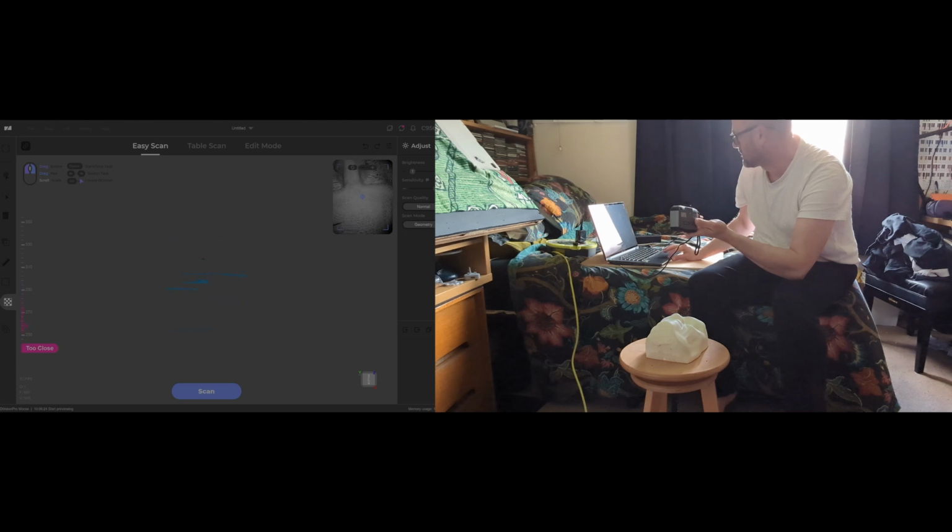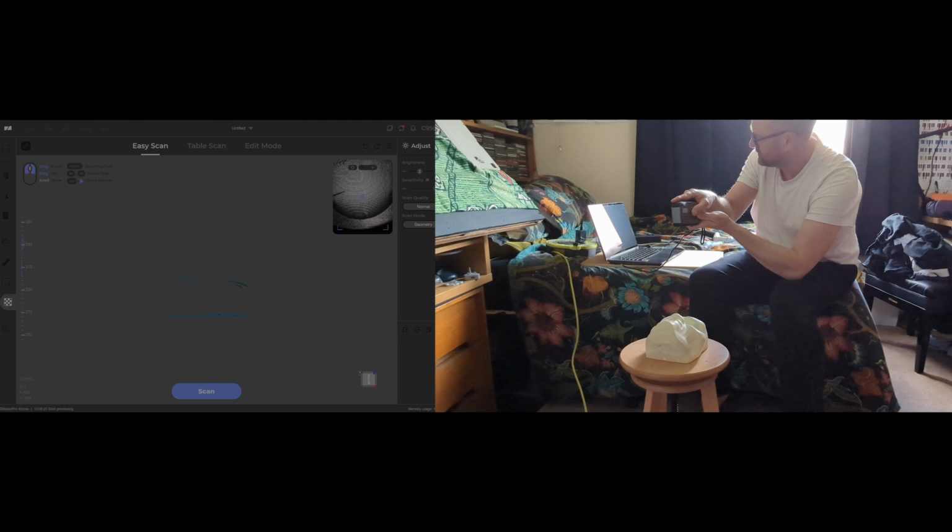look closely on the left hand screen and you will see that there are bars of blue scan lines. That should be a whole block, no matter what the distance is. If you're too close, there'll be a hole in that data, and if you're too far away, it won't read. And what it seems to be doing is reading things like a Venetian blind, which says to me that there's something wrong with one of the actual scanners themselves, the reader. There's something not right there.